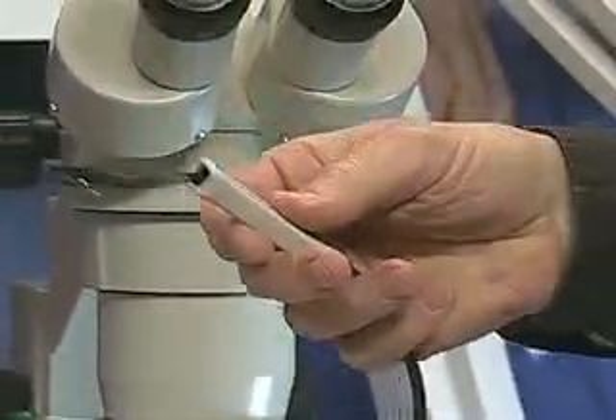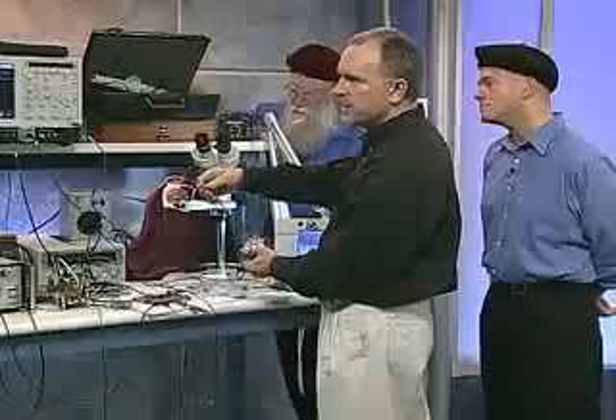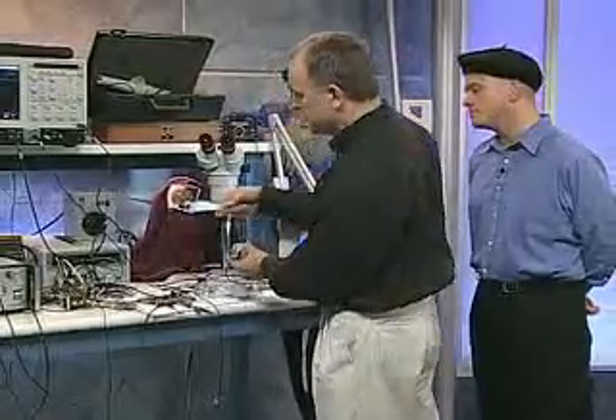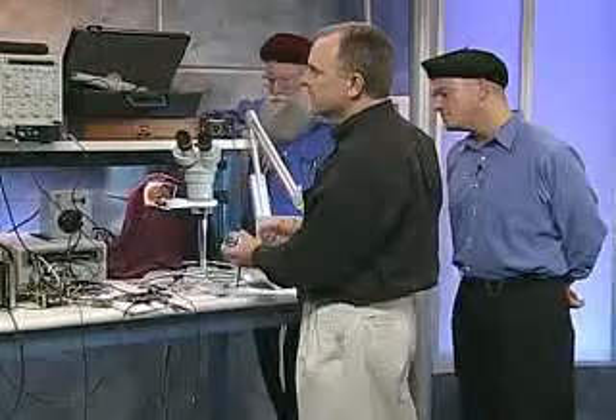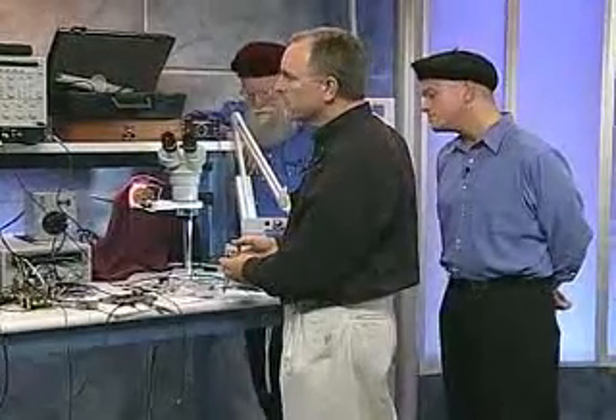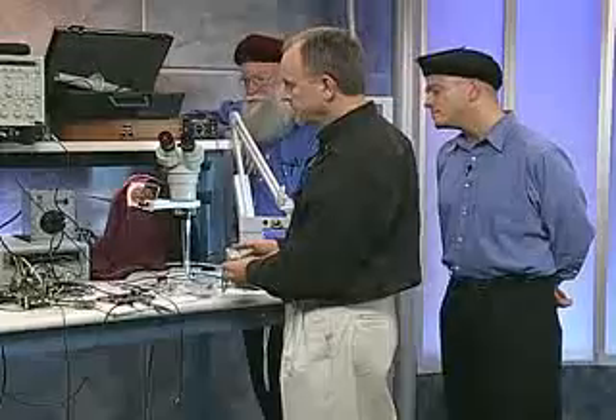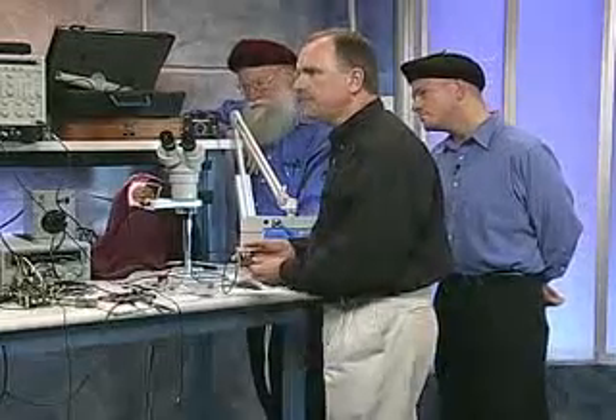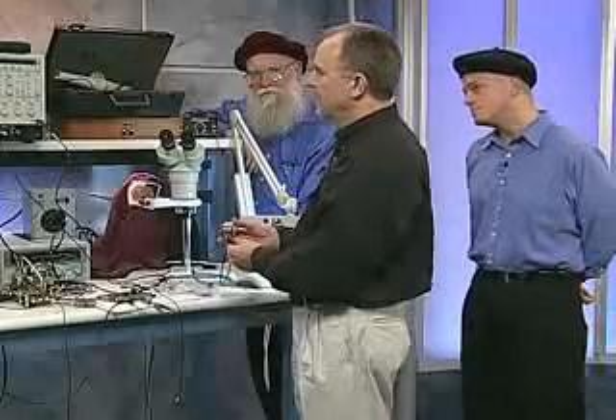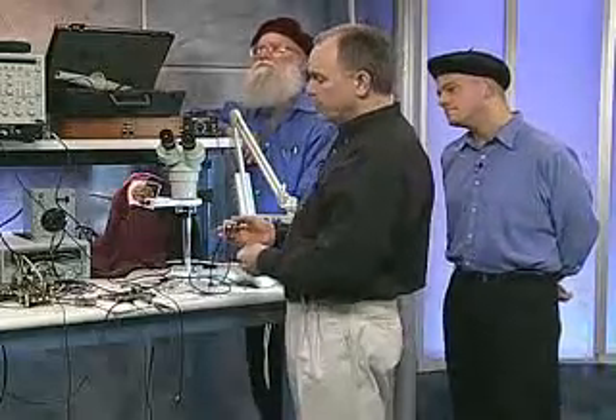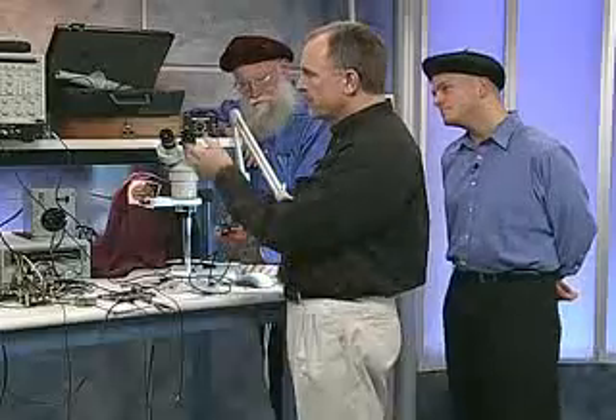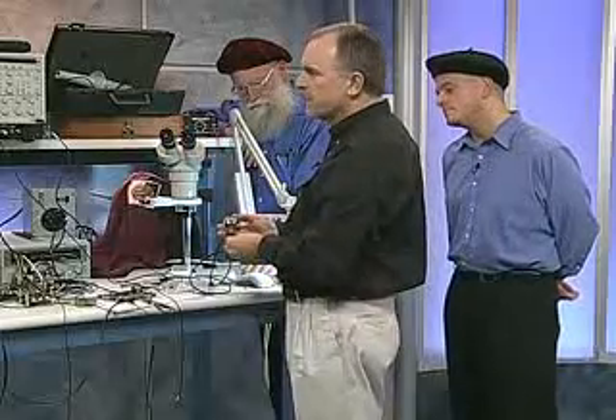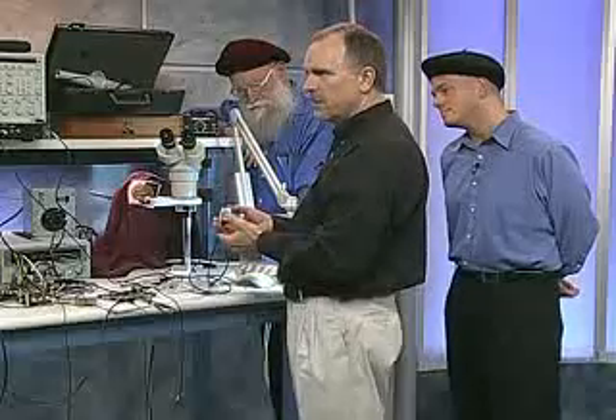So with powered devices, they need DC power supplies from the scope and so forth. So there's a lot of intelligence going back and forth these days between the scope and the probe, and they really are designed as a system. I see. Is there a separate power supply for that probe so I can go into my Tektronix spectrum analyzer? Is that useful for the older probes? For the older active probes that are BNC based, we have a power supply because they can stand alone.